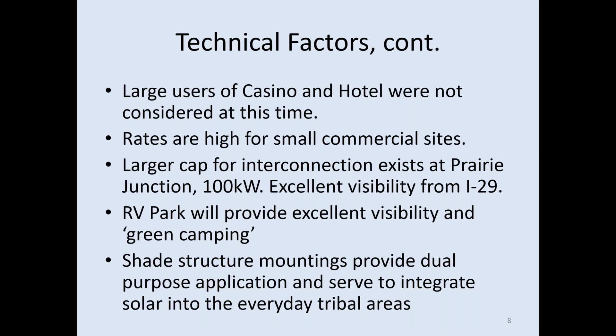This is what was designed for the tribe, using Iron Ridge design software as a base, but we wanted it high enough to clear head height so we could use underneath as a shade structure in the tribal areas. To do that with standard 3-inch pipe, we had to use extended concrete footings to protect it. Note the shallow solar incident angle, 10 to 15 degrees, to reduce uplift at the same time. Next slide, please.